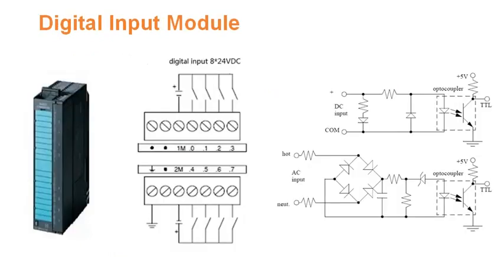Input module shown here is of 24 volts DC digital input module which accepts 8 inputs. Whenever a switch is closed, the 24 volts DC is applied to the input. On the right side top, you can see whenever 24 volts is applied, the opto transistor will be switched on, and this change in signal level is sensed by the CPU.